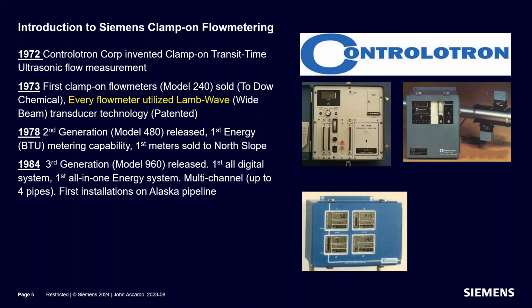In 1984, we released the 960 meter. If you see a pattern going on here, each time we doubled the number. That was kind of to say, this one's twice as good as the previous one. The third generation Model 960 was the first all digital system. Instead of discrete components configuring a circuit board for your application, it was all burnt onto an EEPROM, a small handheld device that you could plug into the system, and it would configure the system for your specific pipe size.